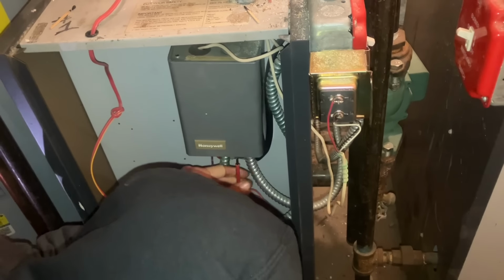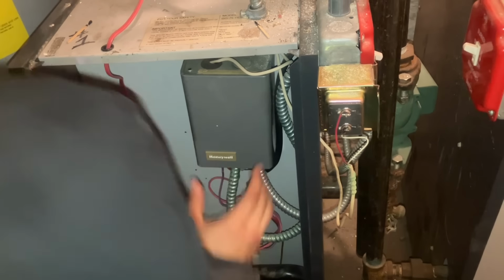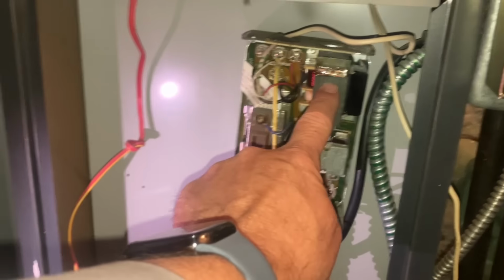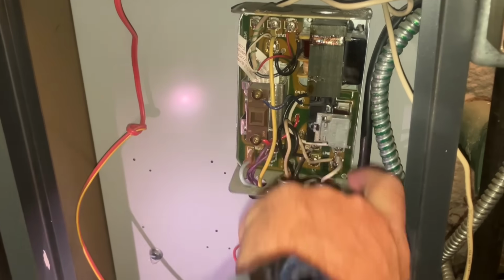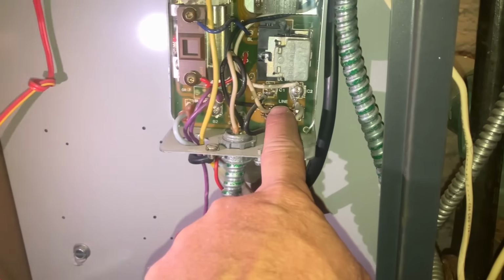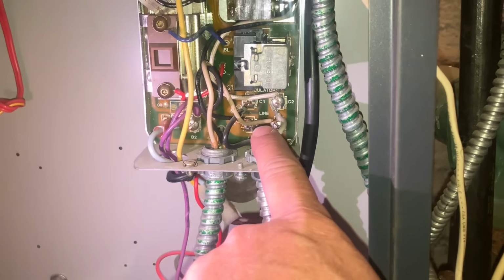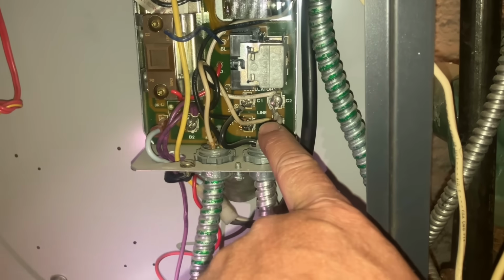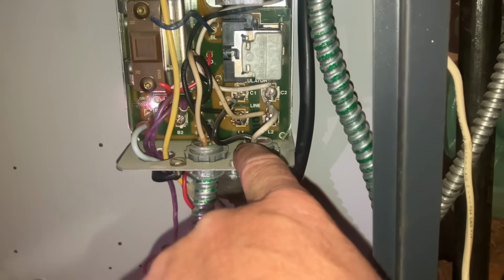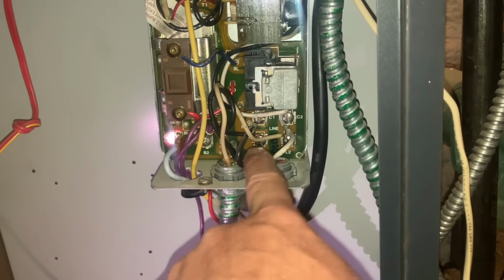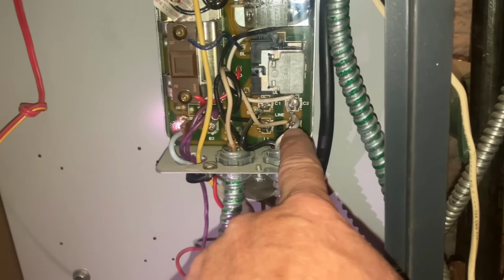Now that all the burners are back into place. Now this is an Aquastat relay, so I'll explain to you what this does. There's our temperature control. That is set to 180 degrees. This is your transformer. This is your relay. Okay. Down here, where it says line, where C1, C2, that's circulator 1, circulator 2. Right below that is L1, L2. So that's line and neutral. Line and neutral also for the circulator.